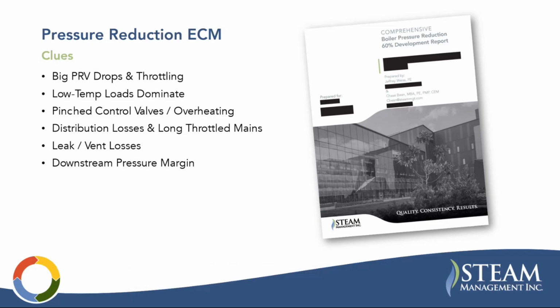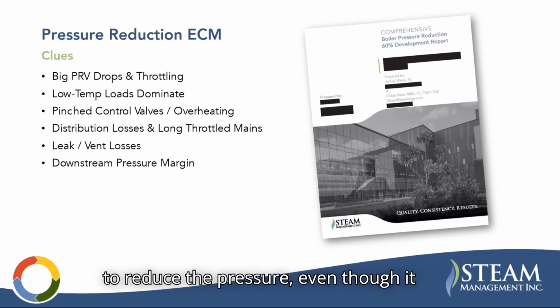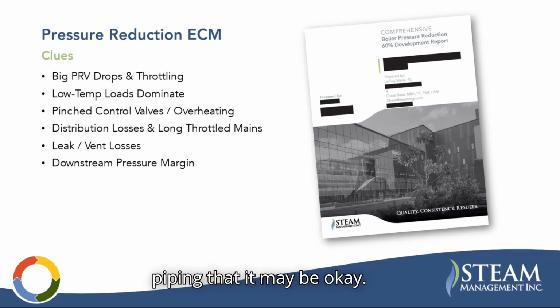And I should point out there too, oftentimes with steam systems, loads are taken off. And so there may be less flow through the system than it was originally designed for. And so you have some room to reduce the pressure, even though it increases the velocity in the pipe and increases the pressure drop. You may be far enough away from the original load that was designed for that piping that it may be okay.